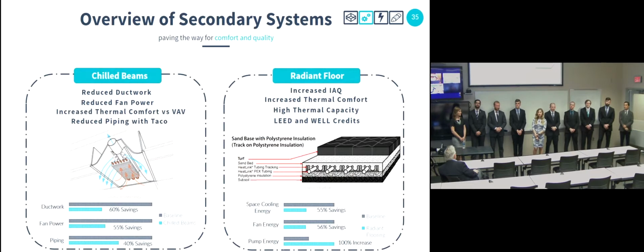The chilled beams located in the north and northwest rooms were chosen over a traditional VAV system because they are able to reduce the amount of ductwork necessary, reduce overall fan power, as well as increase the thermal comfort in the space. Utilizing the TACO mixing boxes, we're also able to reduce the piping that a normal chilled beam system would utilize. The chilled beams will be paired with dew point sensors located in the zones they serve.